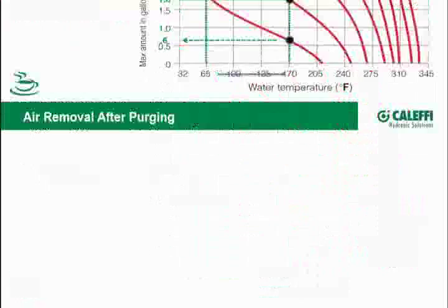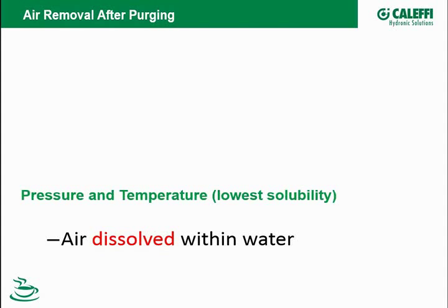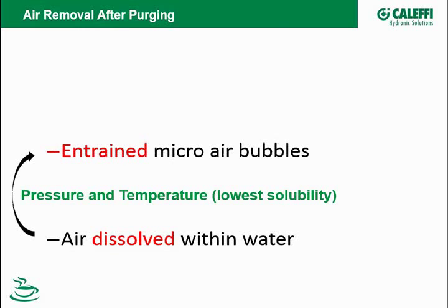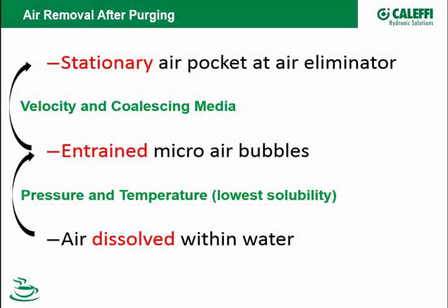How do we find that location? We have water with dissolved air in it. First, look at how to find my lowest solubility point — it's about pressure and temperature. If I choose the right combination, my dissolved air becomes entrained micro air bubbles. Once I have those micro air bubbles, they're small and subjected to all the velocity and dynamics — very hard to separate. So I have to have a way to get the bubbles to a format where they will make their way up to an air vent. We use velocity and a coalescing media to change small entrained micro bubbles to a stationary air pocket within my air eliminator. Once I have a stationary air pocket, I can get rid of the air with an air vent.